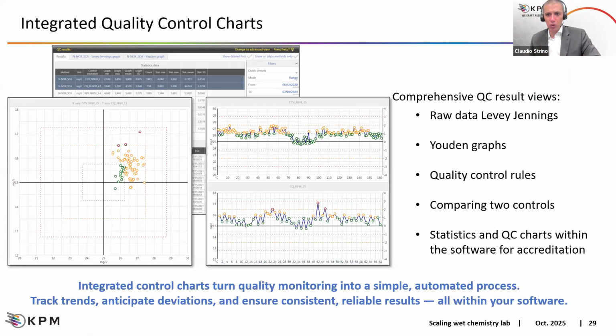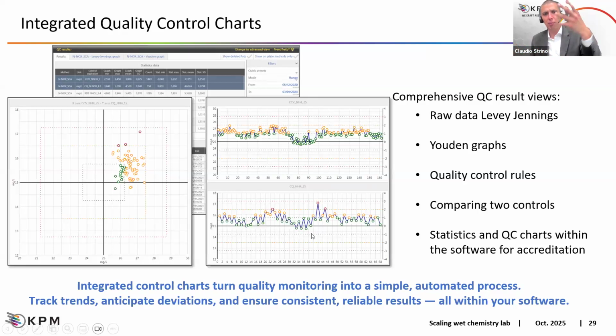Again, to help labs also during the accreditation, we have built-in QC charts, both Levey-Jennings and Westgard charts, where we can not only see the trend over time for a QC, but in the same window for the same method, we can also compare two QCs, for example, high QC and low QC, because we can monitor the trend of both. If the high QC is okay and the low QC is not, we can further address the low QC, checking how we are preparing the QC and so on. So we can also be part of the evaluation process thanks to the information we can obtain from the SmartChem software.